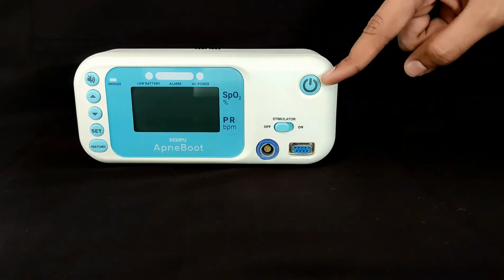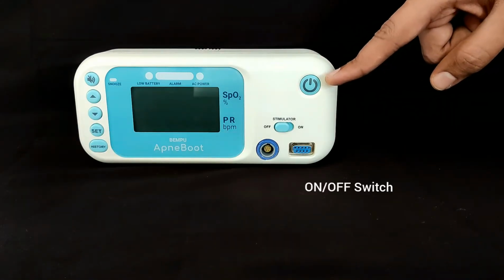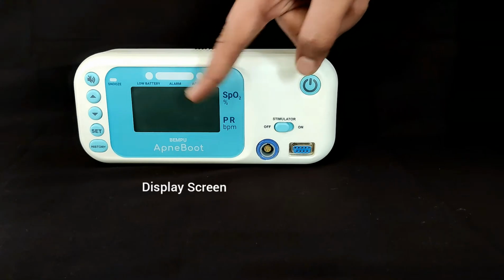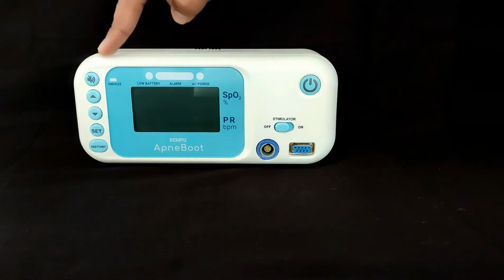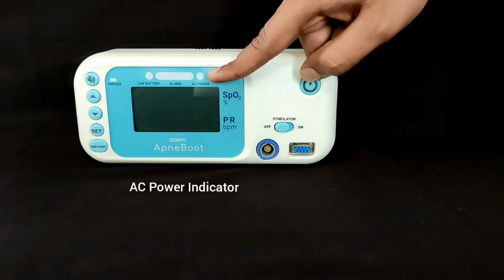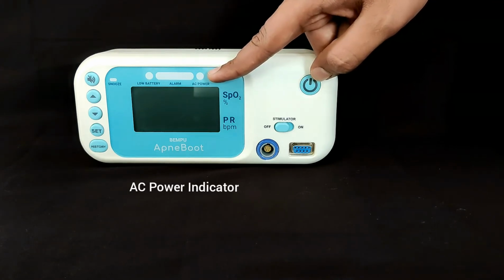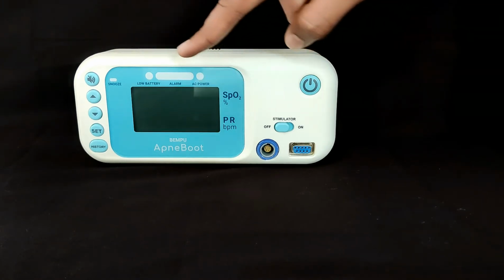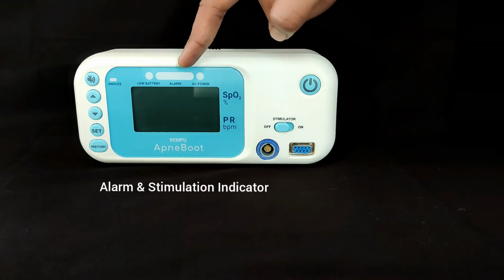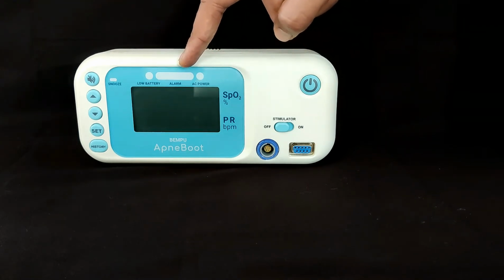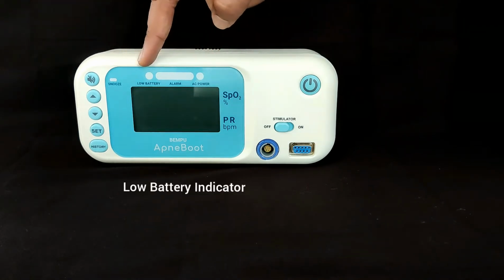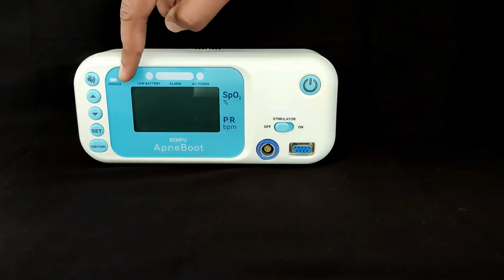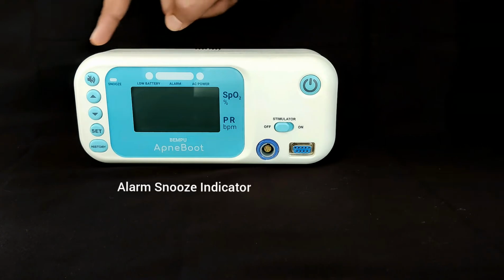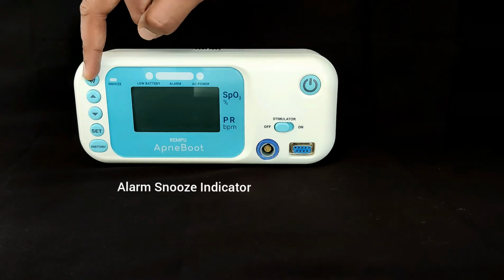On the front side of the device, this is the device on-off switch, the display screen, and a series of 4 LEDs. The first LED turns on if the device is running on AC power supply. This LED in the center turns on when the device alarms and stimulates. The next LED turns on when the device is operating with low battery, indicating to recharge. And the next LED in the corner turns on when the alarm is snoozed by pressing the adjacent alarm button.